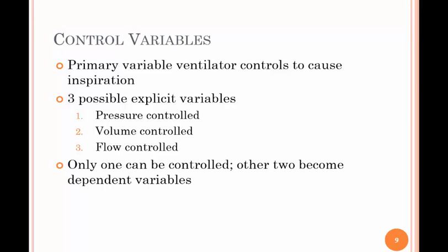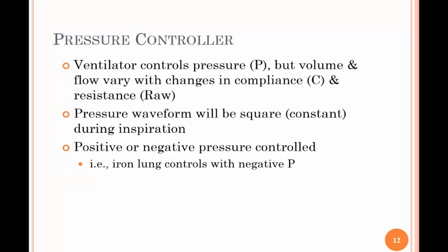Inside the control circuit we have control variables — the primary variable the ventilator controls to cause inspiration. There are three of them: pressure, volume, and flow. Only one of these can be controlled and the other two become dependent variables. The pressure controller means the ventilator controls the pressure, but volume and flow vary with changes in compliance and resistance.